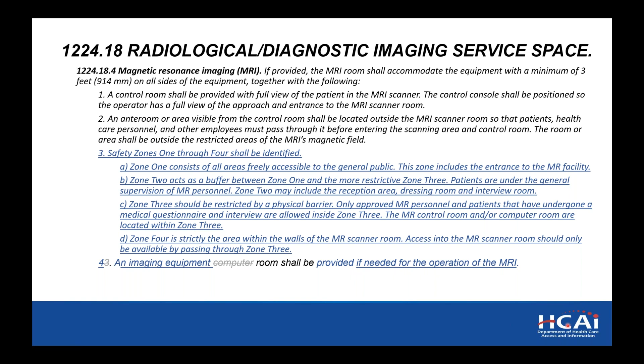Also, a lot of the new imaging equipment is coming out with much less equipment that goes along with it. So the imaging equipment room, or the computer rooms that we used to call them, may or may not be needed. It's going to be based on the type of imaging equipment you have. We're seeing a lot of the CTs are little CPU-sized boxes that can sit under the control desk. So depending on the type of equipment, you'll see a lot of language here that says an imaging equipment room. We're standardizing the wording to imaging equipment room because we've seen computer room, electronic room, equipment room, all kinds of stuff. So they're all going to be imaging equipment room shall be provided if needed for the operation of the MRI. Because a lot of the equipment no longer requires the equipment room.